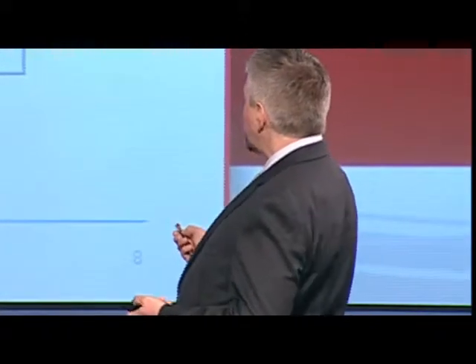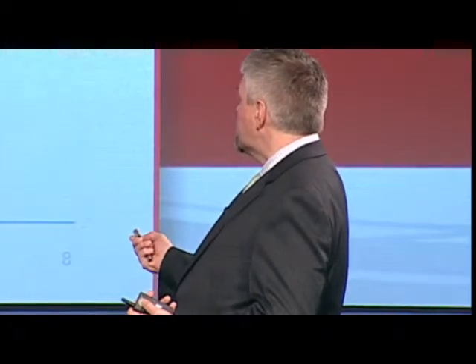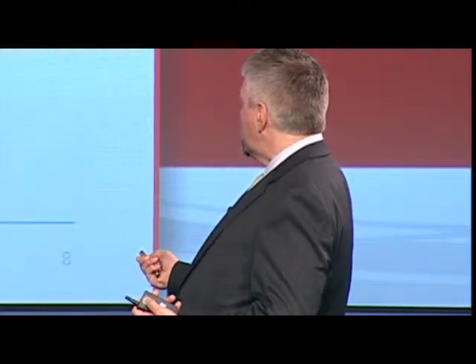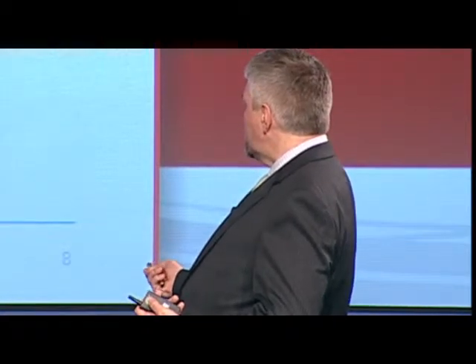This picture here shows the tests we ran: 60°F at 0.4 inches of water column — basically a good breeze, about one millibar of positive pressure — then 65°F at 0.4, 75°F at 0.2, 75°F at 0.1, 78°F at 0.4, 80°F at 0.4, 85°F at 0.4, 86°F at 0.2, and 89°F at 0.1. Those are the tests that we ran.